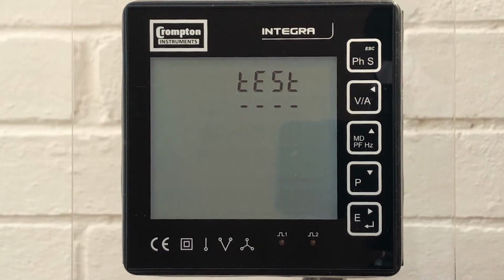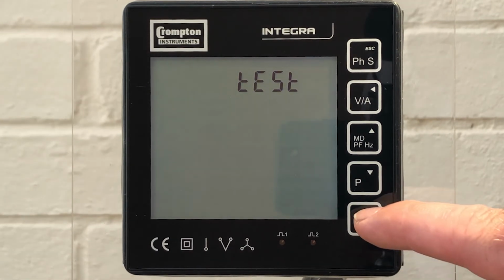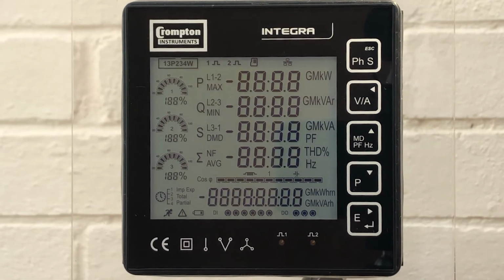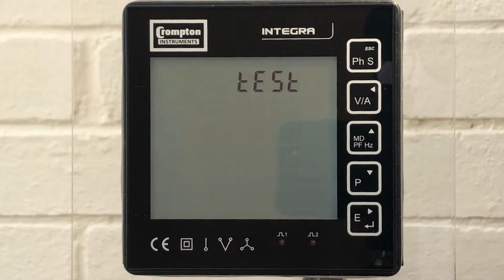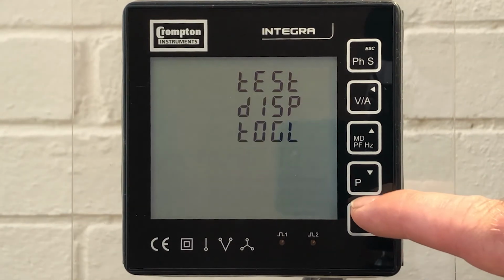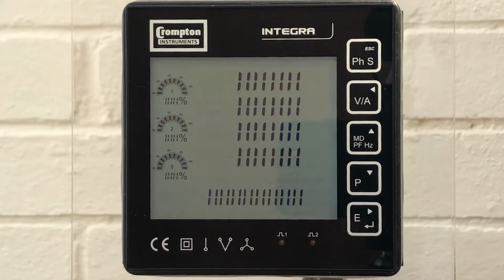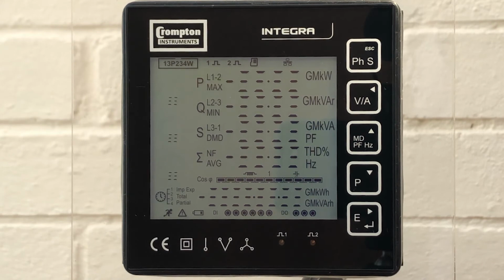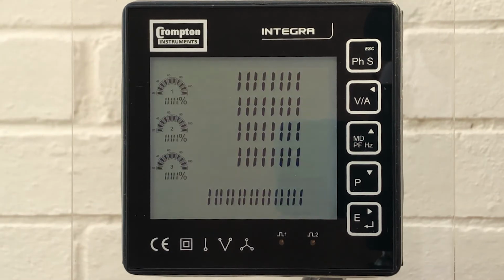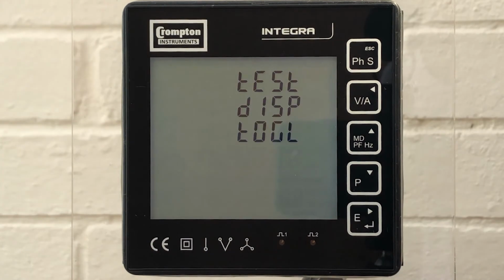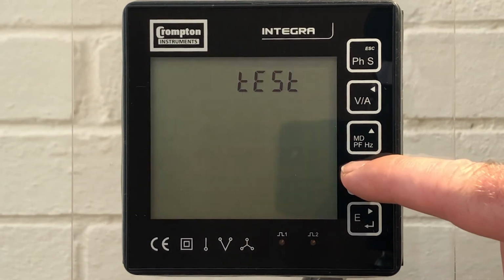Arrow down to the test, to check the display segments. Available options are display on, and you can see that Integra will check all of its display segments are working correctly. If we select display toggle, this is where half of the segments will light up in one screen and the rest in another, and the meter will continuously switch between the two for visual checks.